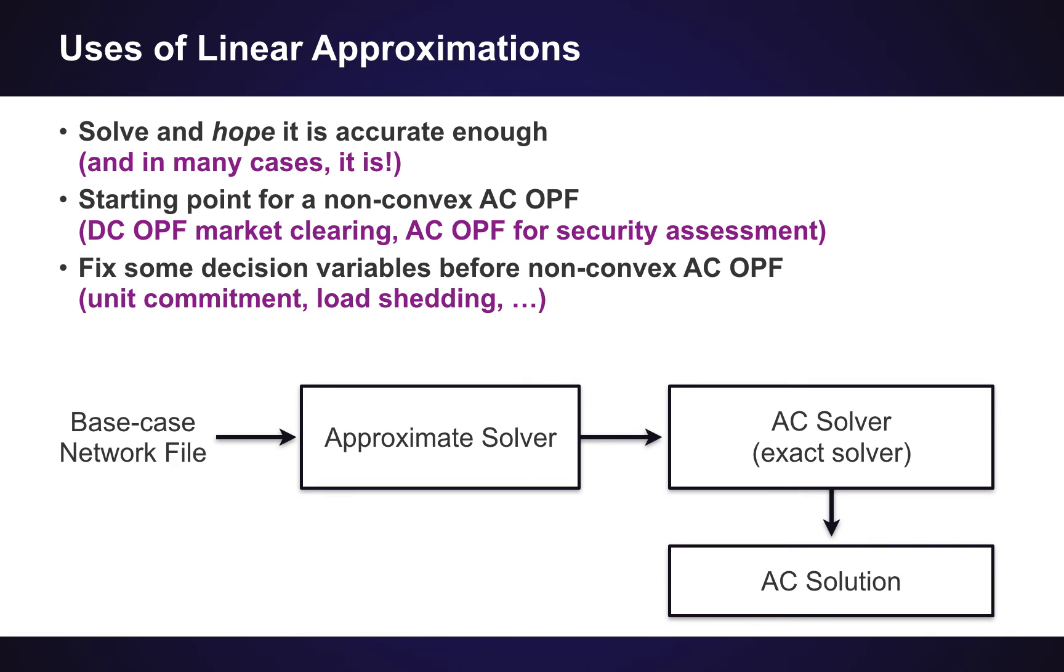And so how are we then using those linear approximations? Because clearly, we need to be a bit careful when we are using them. So maybe the most used approach is just to solve the problem using a linear approximation and just hope that the solution is accurate enough. And actually, in many cases, it is really good. Another possibility is to use the linear approximation as a starting point for a non-convex AC optimal power flow problem. And an important practical example of this is when we are using the DC optimal power flow for market clearing problems, which is typically done in the United States. So all power system markets that are liberalized are typically cleared using this DC power flow approximation. And then the solution that comes out of this market clearing is then fed into an AC optimal power flow problem, which is used to make sure that the solution that we have is actually going to be secure to use in operation and not violate any of the bounds that we need to observe in practical operations.